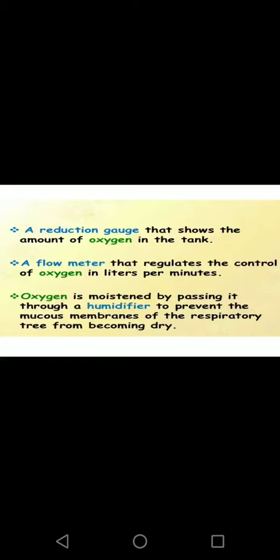A reduction gauge shows the amount of oxygen remaining in the tank. A flow meter regulates the flow in liters per minute. Oxygen is moistened by passing it through a humidifier to prevent the mucous membranes of the respiratory tree from becoming dry. The flow meter also has a humidifying chamber, flow adjuster, pressure gauge, and safety valve.